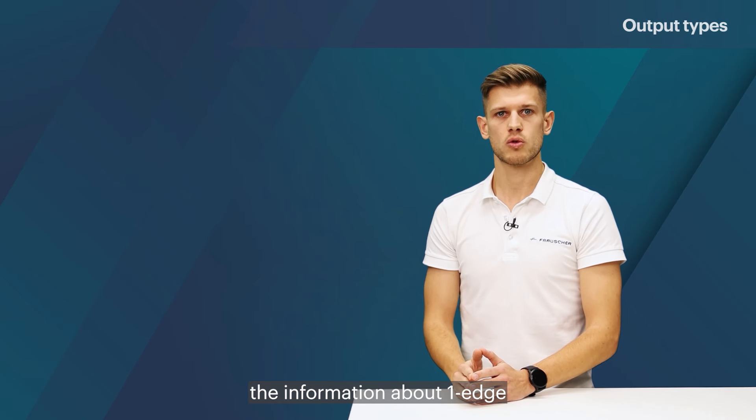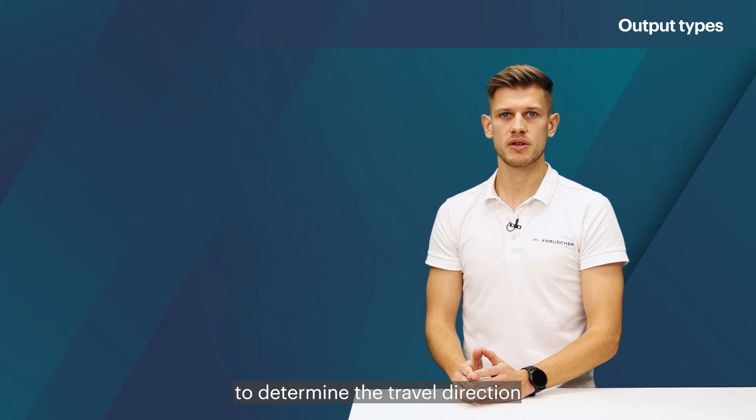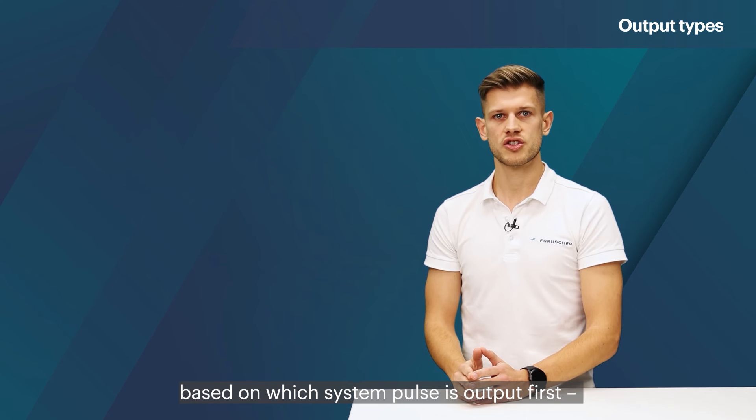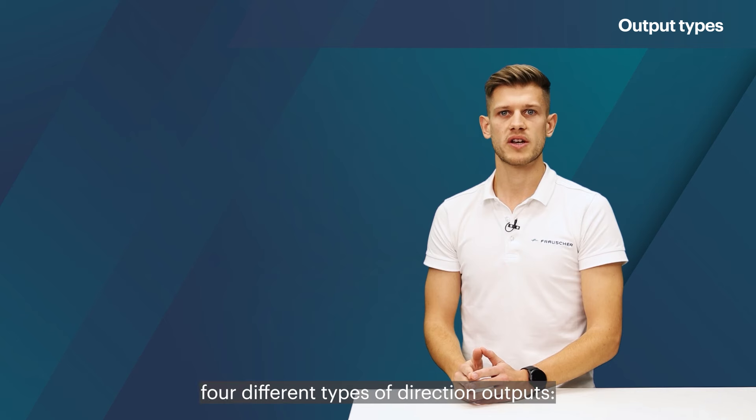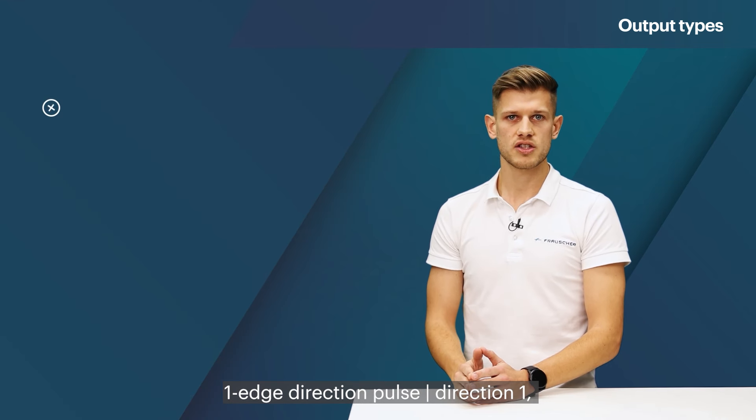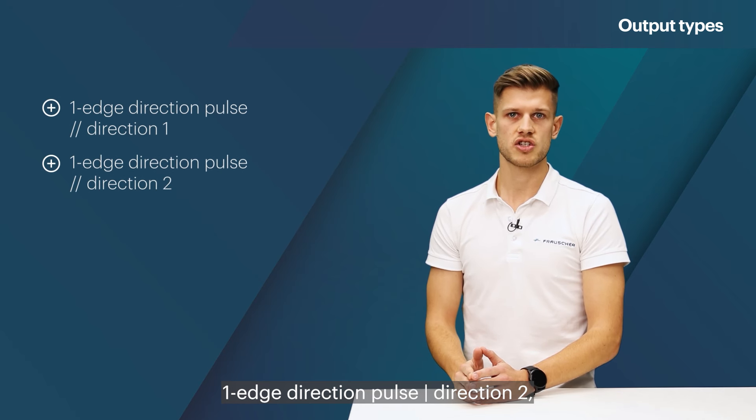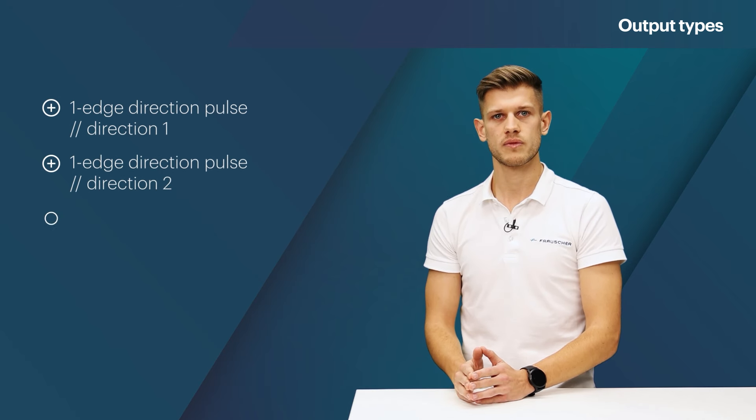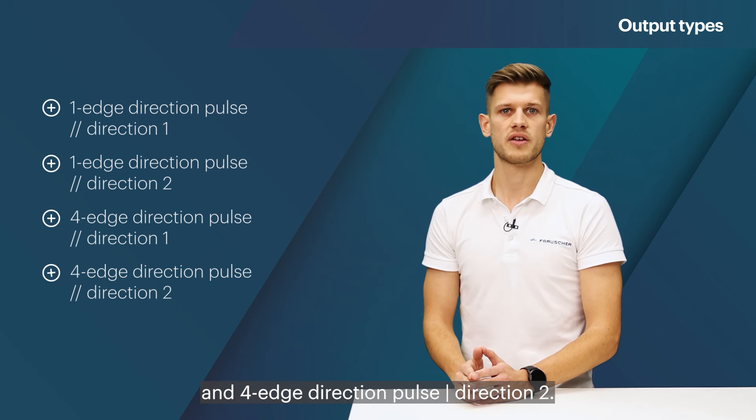Combining the information about one edge and four edge pulses with the ability to determine the travel direction based on which system pulse is output first, makes it possible to provide four different types of direction outputs: one edge direction pulse direction 1, one edge direction pulse direction 2, four edge direction pulse direction 1, and four edge direction pulse direction 2.